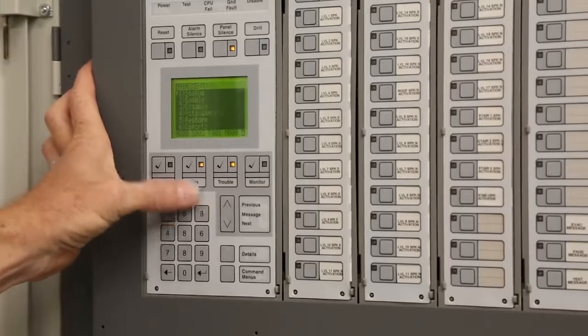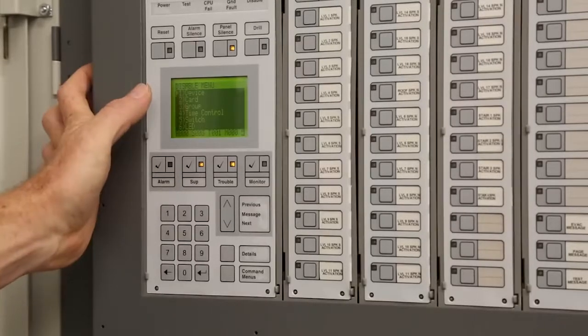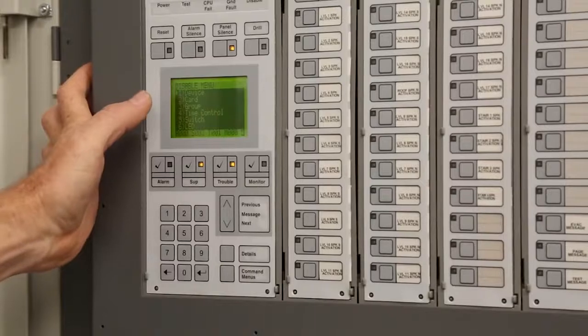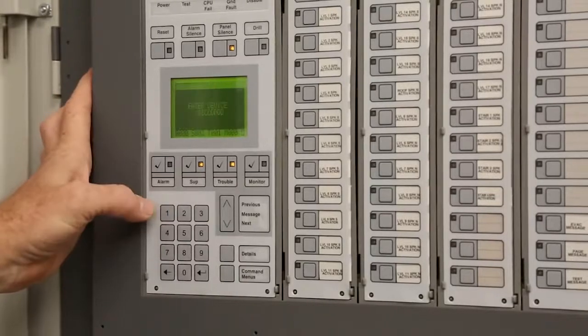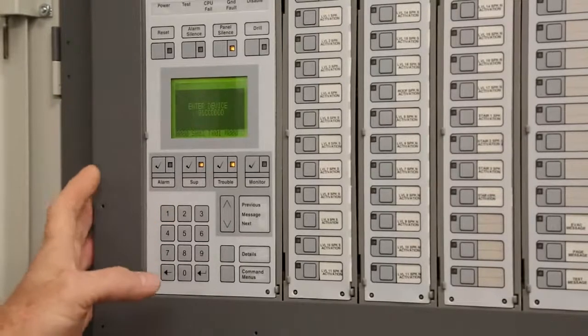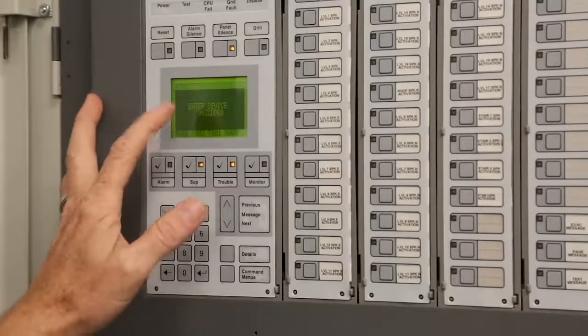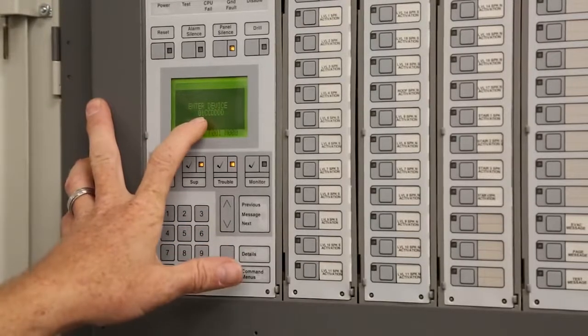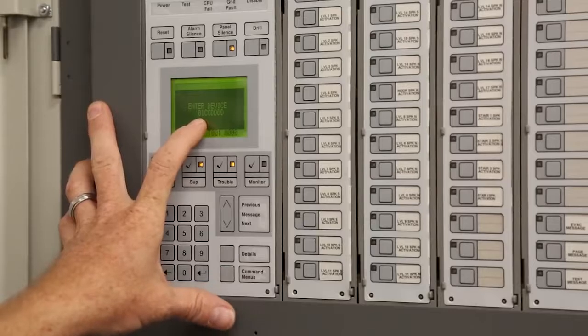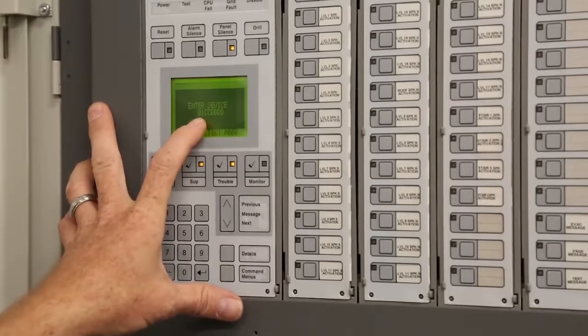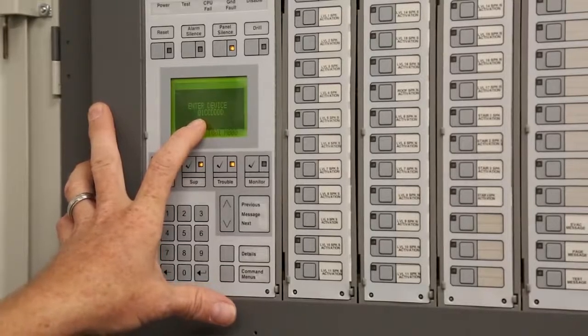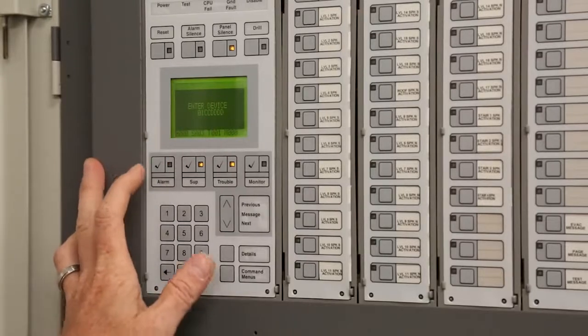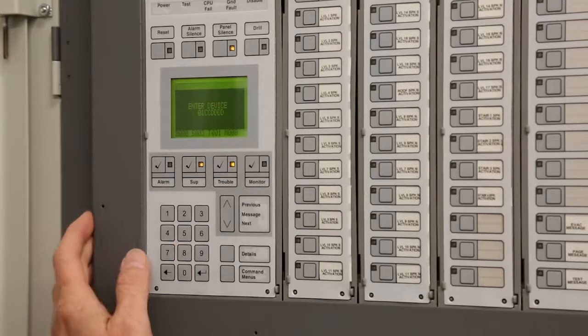You hit number 3 for disable, and it's going to ask you, do you want to do the device or a card? For you all, it's going to be a device. And there is 2 panels in this place. So the first number right here represents what panel you're at. Every detector has a marker on it. So on this side, for instance, it's all 01. Hotel is going to be all 02.